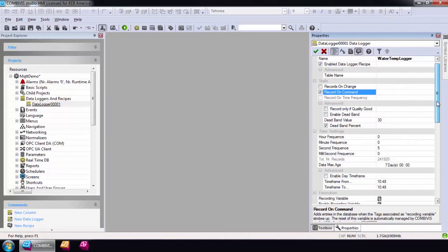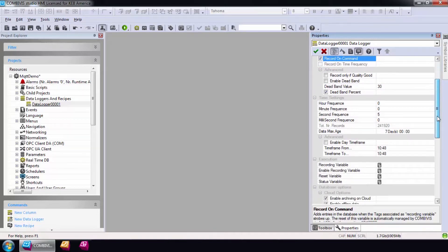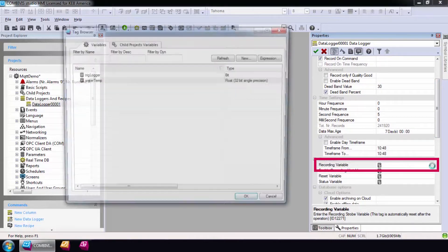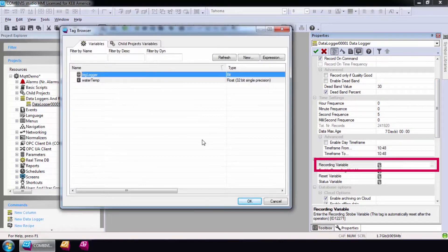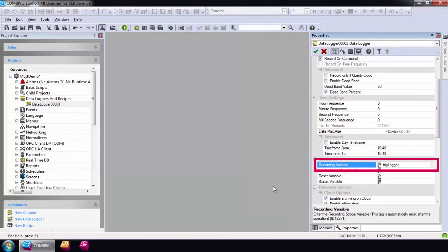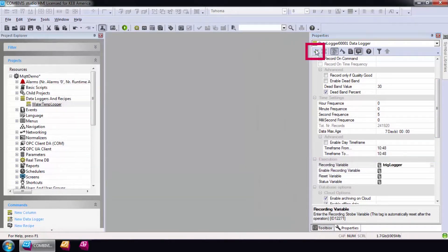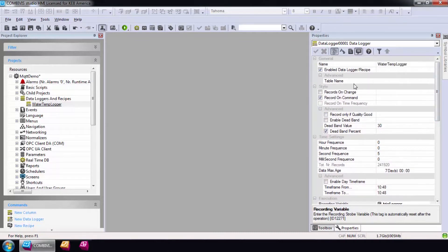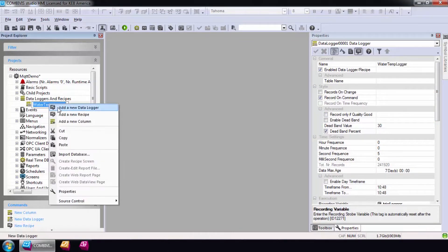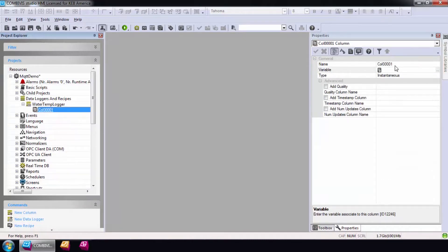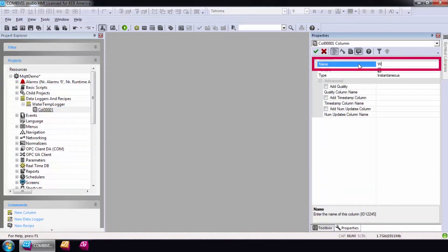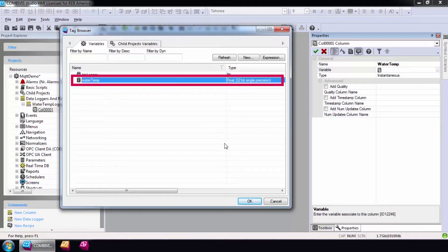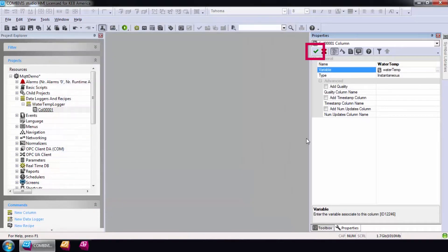My PLC program will trigger the recording value every six seconds and the data logger will automatically set the trigger back to false. Therefore, I will check record on command and enter the trigger in the recording variable. Each data logger contains columns for data. I'll use the tag WaterTemp as the only column in this example and select the green check mark to save my changes.